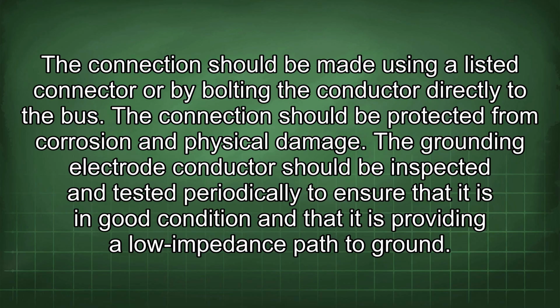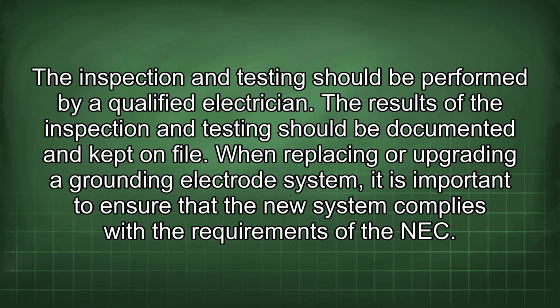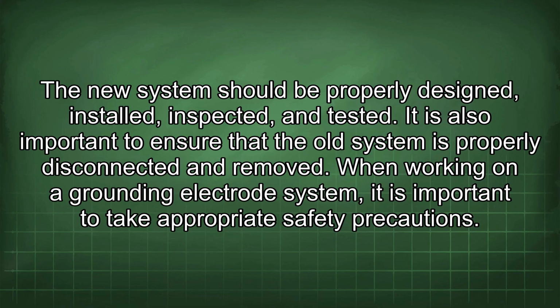The grounding electrode conductor should be inspected and tested periodically to ensure that it is in good condition and that it is providing a low impedance path to ground. The inspection and testing should be performed by a qualified electrician. The results of the inspection and testing should be documented and kept on file. When replacing or upgrading a grounding electrode system, it is important to ensure that the new system complies with the requirements of the NEC. The new system should be properly designed, installed, inspected, and tested. It is also important to ensure that the old system is properly disconnected and removed.